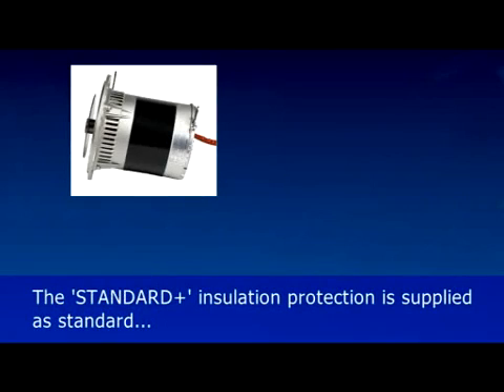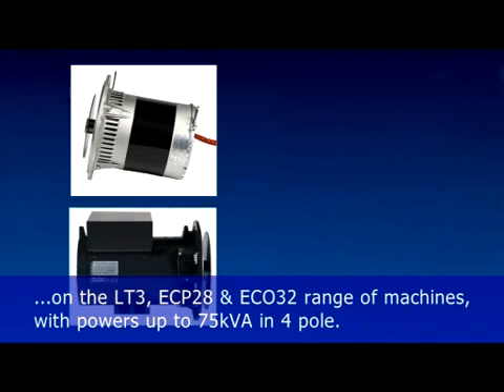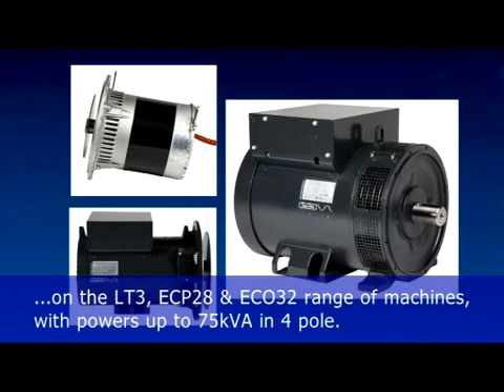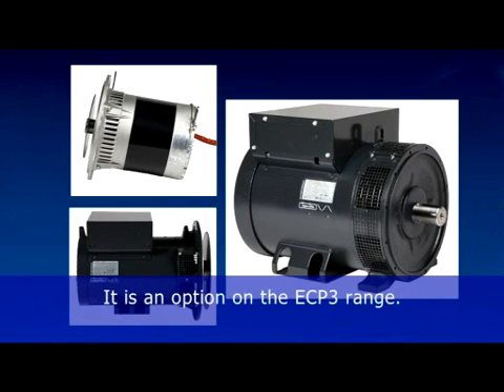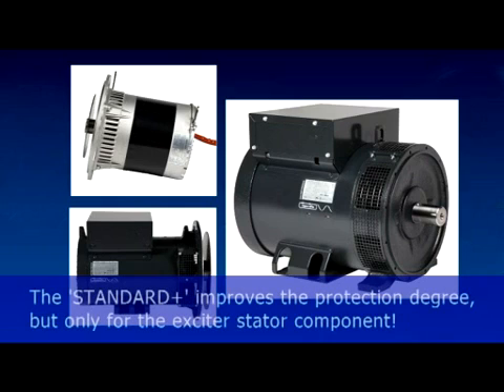The Standard Plus insulation protection is supplied as standard on the LT3, ECP28 and ECO32 range of machines, with powers up to 75 kVA in 4-pole. It is an option on the ECP3 range. The Standard Plus improves the protection degree, but only for the exciter stator component.